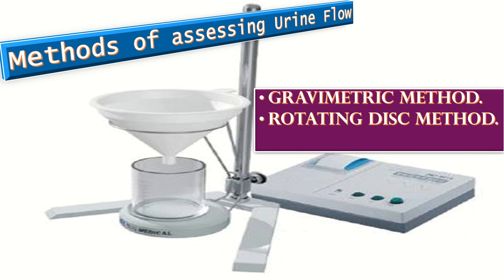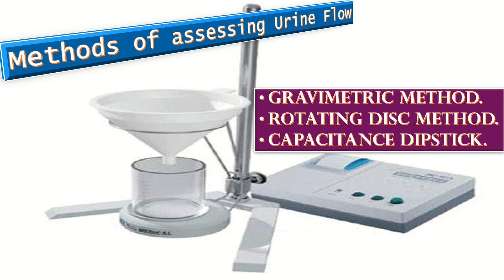What are the different methods of assessing urine flow? The three commonly used methods include: first, the gravimetric method, in which the rate of change of the weight of voided urine is measured. The second is the rotating disc method, in which the voided fluid is directed onto a disc, increasing its inertia, and the flow rate is proportional to the extra power required to keep the disc spinning at a constant rate. The third is the capacitance dipstick method, in which a metal capacitor strip is attached to the side of the flow meter.